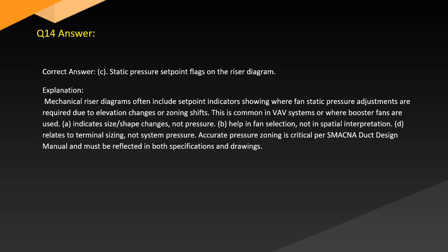Answer. Correct answer: C. Static pressure setpoint flags on the riser diagram. Explanation. Mechanical riser diagrams often include setpoint indicators showing where fan static pressure adjustments are required due to elevation changes or zoning shifts. This is common in VAV systems or where booster fans are used. A indicates size and shape changes, not pressure. B helps in fan selection, not in spatial interpretation. D relates to terminal sizing, not system pressure. Accurate pressure zoning is critical per the SMACNA duct design manual and must be reflected in both specifications and drawings.